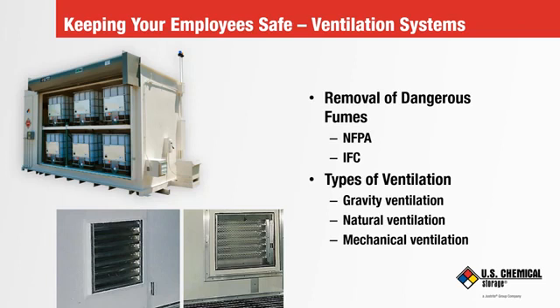Now, when a chemical storage building is installed inside a larger building, the fan must be installed on the roof or wall of the user's building. Negative pressure must be maintained all the way from the chemical storage building through the duct to the fan.